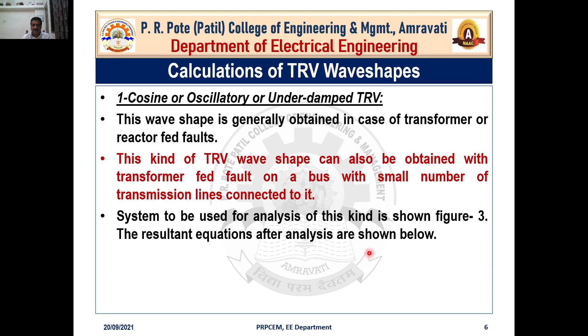This kind of TRV wave shape can also be obtained with a transformer fed fault on a bus with a small number of transmission lines connected to it. In that case also you can obtain this oscillatory, underdamped, or one-cosine TRV. Here we can use the system we showed in the earlier diagram, and obtain some resultant equations after analysis, which we are representing here.